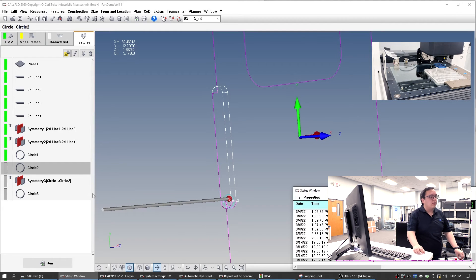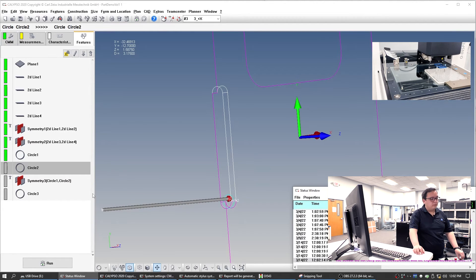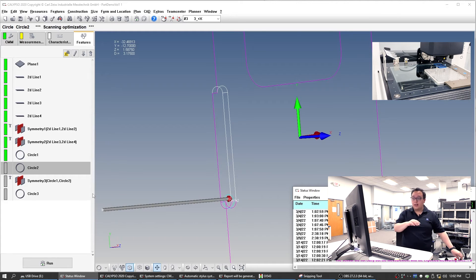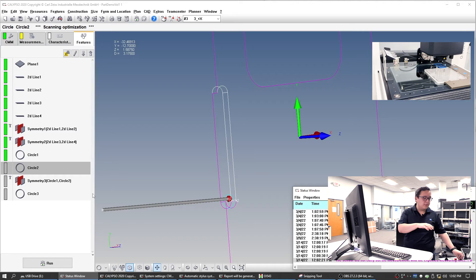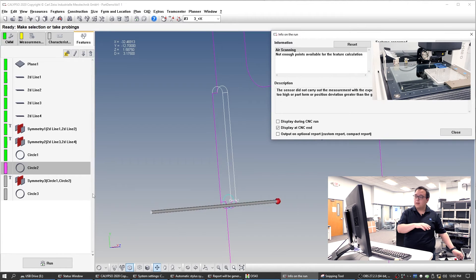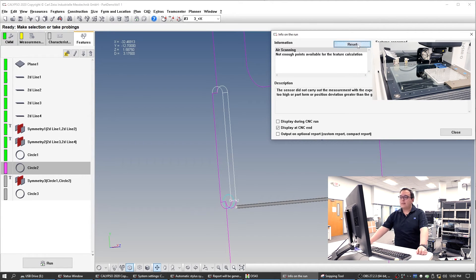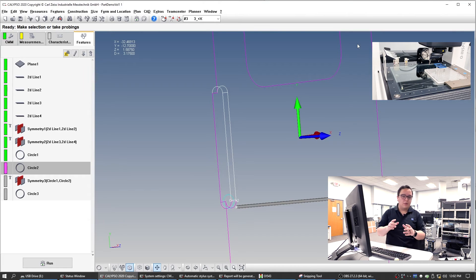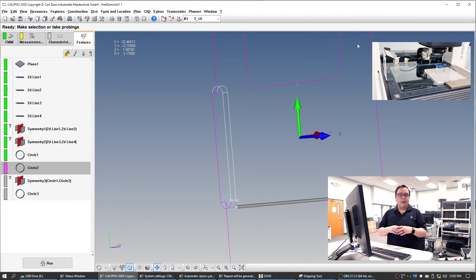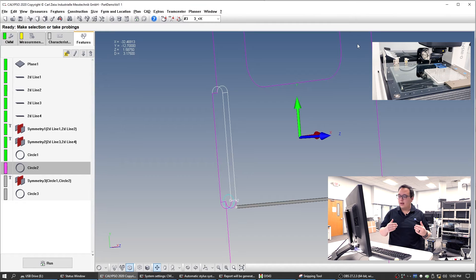There you go. So something it did was it actually went in twice — this is called scan optimization. What it does is: if it doesn't measure something correctly, it goes and measures it again, making sure it's getting the right info. It also gave us a little warning saying that it was air scanning — so it thought where the part should be and where it is is a little different. But it's actually doing exactly what we need it to.